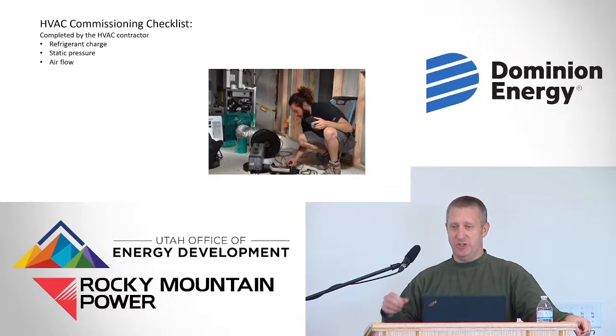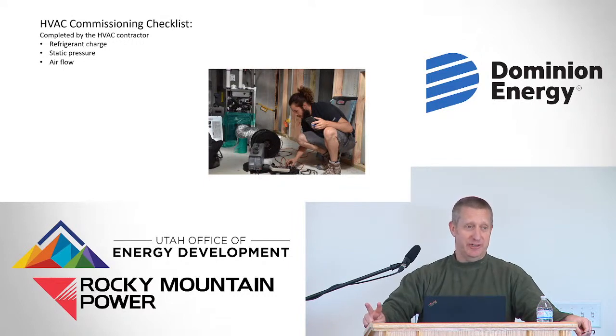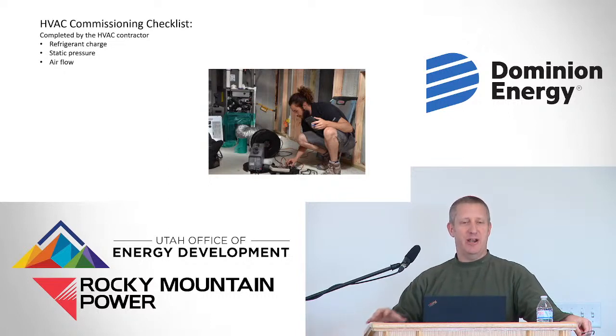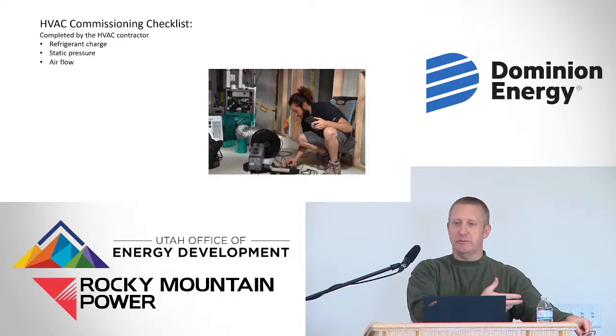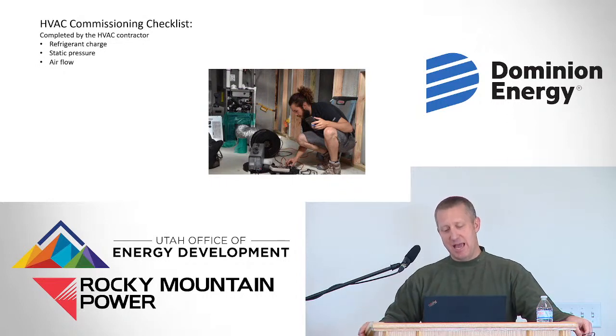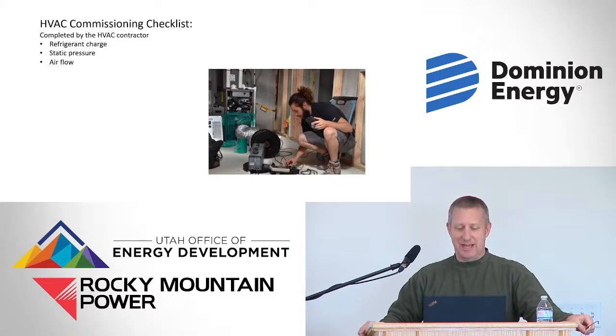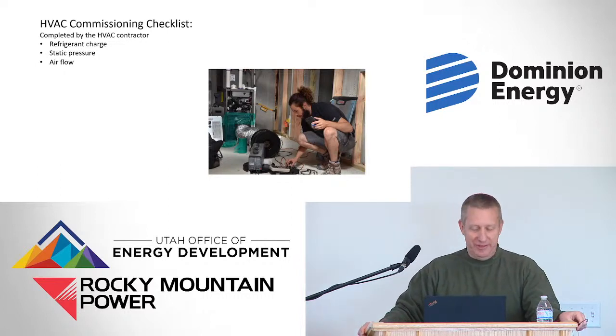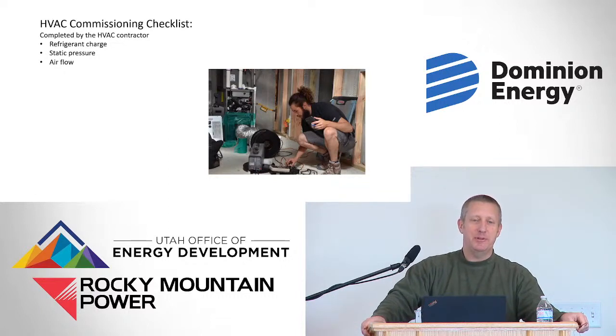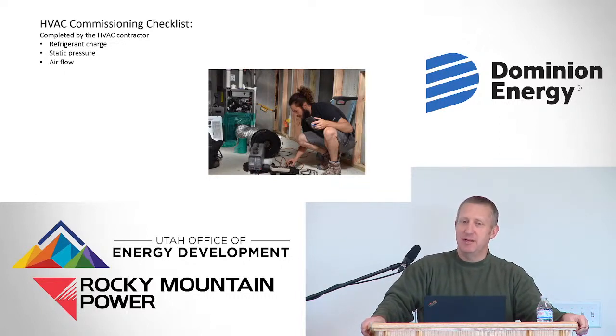And really what we're trying to ensure is that the refrigerant charge is correct, and that the static pressure in the system is correct, and that the static pressure and airflow are related to each other, so that you're really making sure that as much air as is supposed to be moving through each register is. And even though you're buying a brand new home, there's no guarantee that that is happening correctly. So really what this checklist is asking people to do is just to make sure the HVAC system is functioning the way it was installed to function.